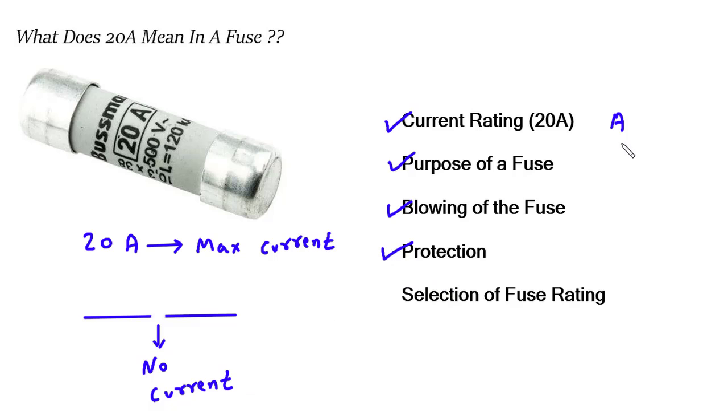Selection of fuse rating. The fuse rating is chosen based on the maximum current that the circuit is expected to draw under normal operating conditions. It should be rated slightly higher than the normal operating current to allow for brief surges in current without blowing unnecessarily. However, it should also be low enough to provide adequate protection against overcurrent situations.